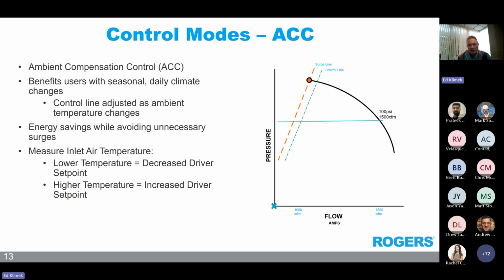The X is the compressor operating point. The control line would be established also during commissioning. So the compressor loads to its minimum operating point and then loads to the required capacity and the compressor will throttle towards its minimum operating point, similar to the operation of suction throttle. But then as the inlet air temperature decreases, the control line will adjust, allowing for that additional turn down and energy savings.